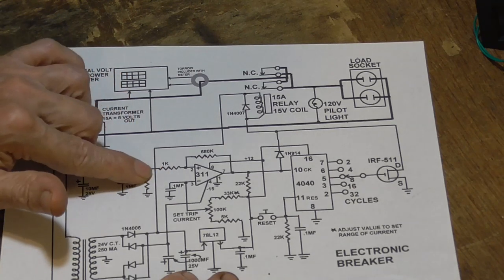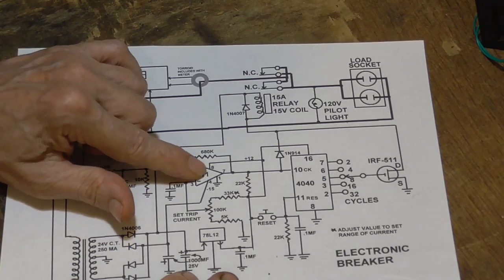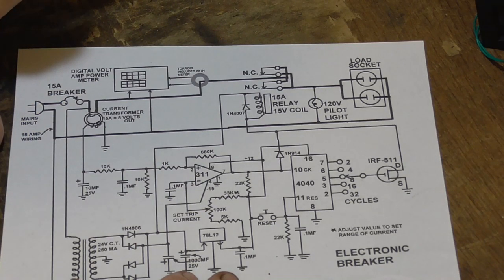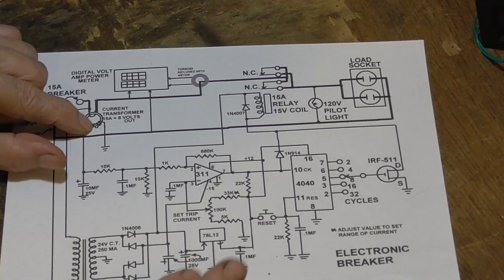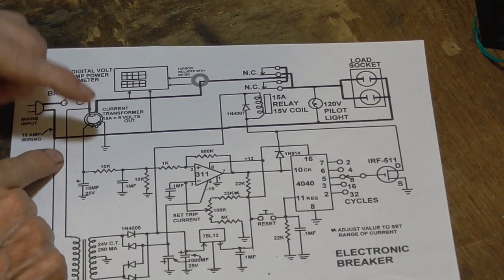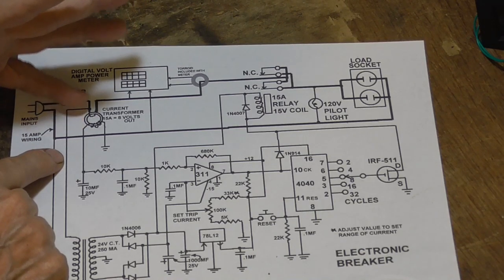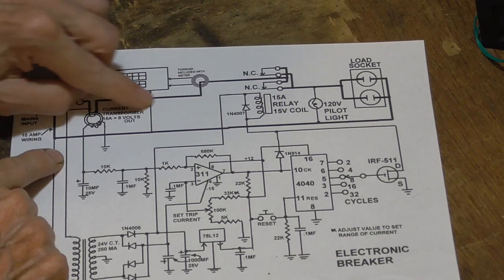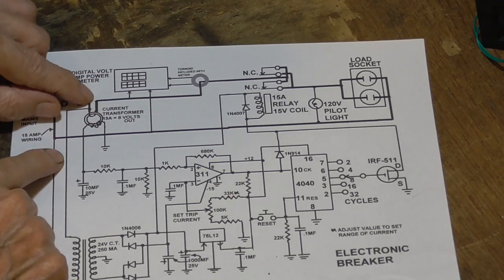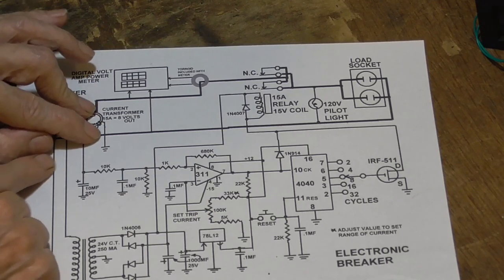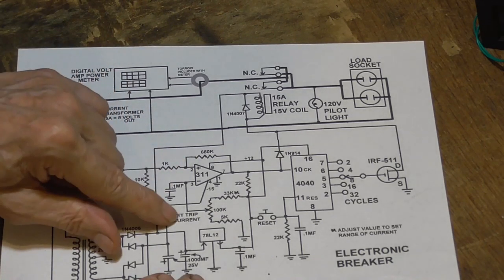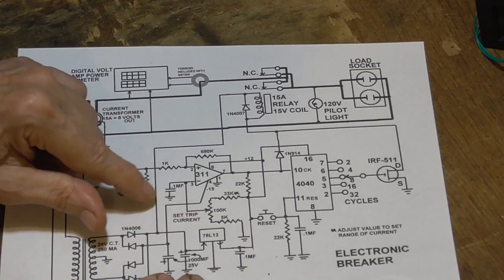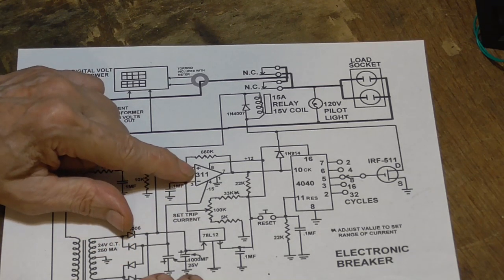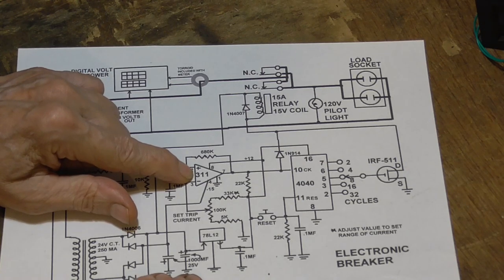We feed the output of that into a comparator, which is our basic detector of the voltage level we're going to trigger on. We'll set the current transformers so we have 0 to 5, 8, or 10 volts for a current range of 0 to 15 amps, adjusting that by the number of turns. We'll have our trip current adjustment, and use it to set the reference on the comparator. So if you're below the trip point, nothing happens.